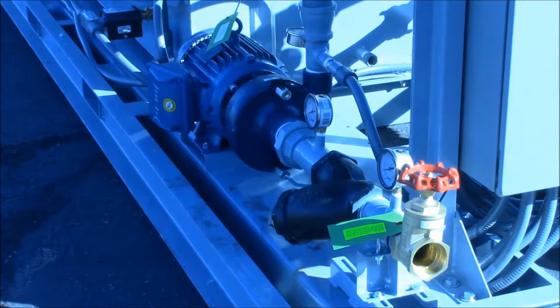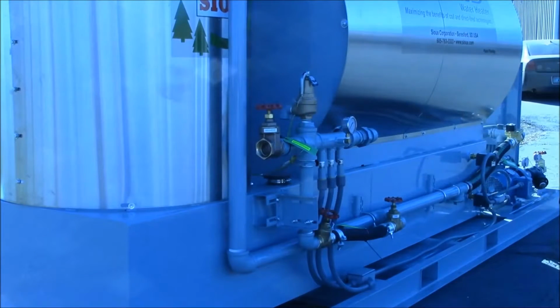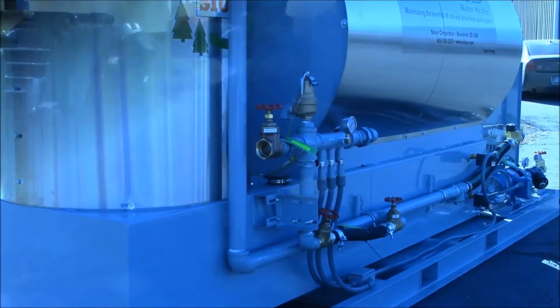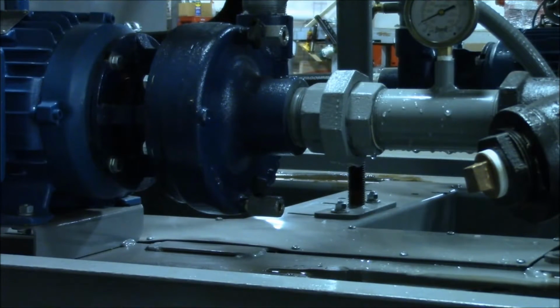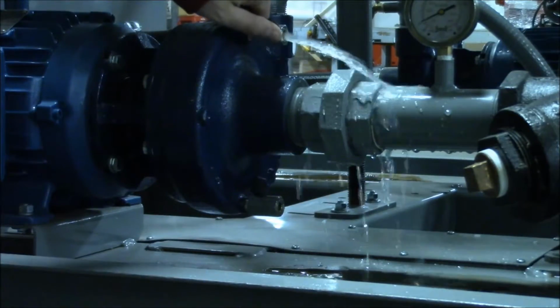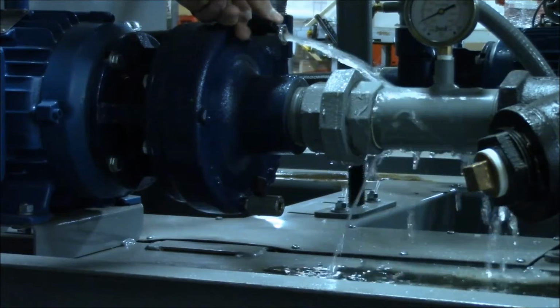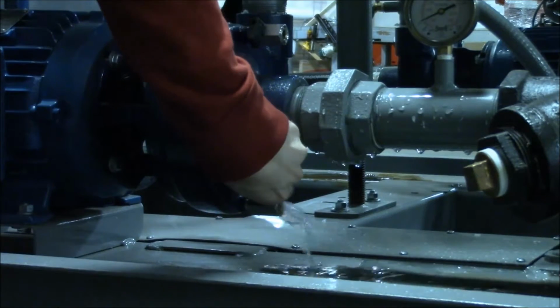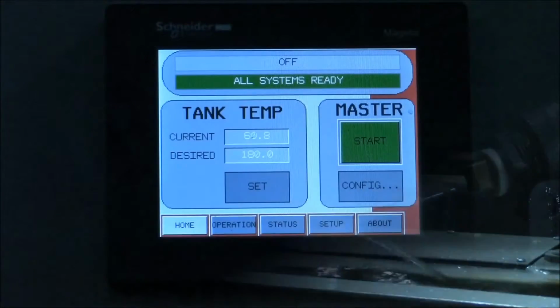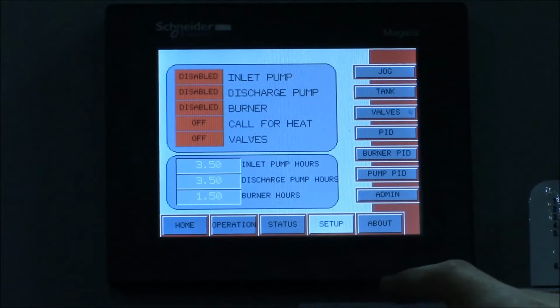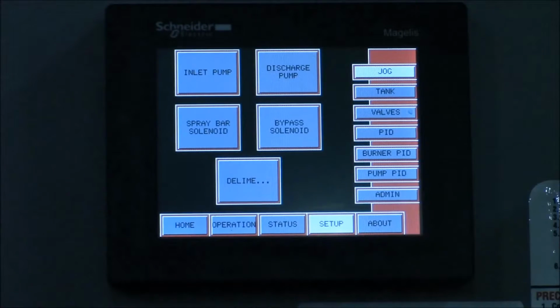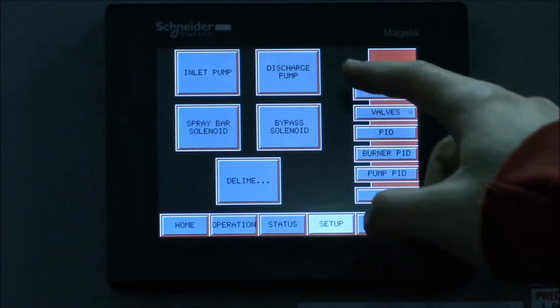Open the water lines to the inlet and outlet of the machine. Ensure that the 2 descaling loop valves are closed. There are 2 priming valves located on each pump. Open the top valve and allow any trapped air to bleed from the pump body. The pumps can be jogged to accelerate this process. To do this, navigate to the setup screen, then select the jog tab and select the pump to be jogged.